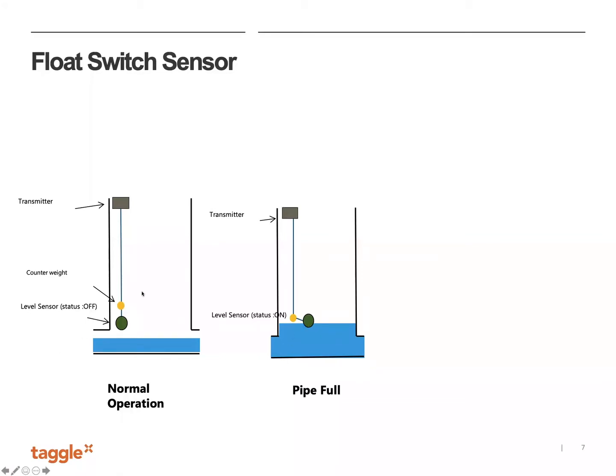And so in the normal operation on the left-hand side here, we would see that a float switch should be off if the pipe isn't full. By strategically positioning the first float switch, as the sewer pipe reaches capacity and starts to fill the well in the manhole, this first switch will actually activate and send a message to the transmitter that then sends a message back to the cloud software.